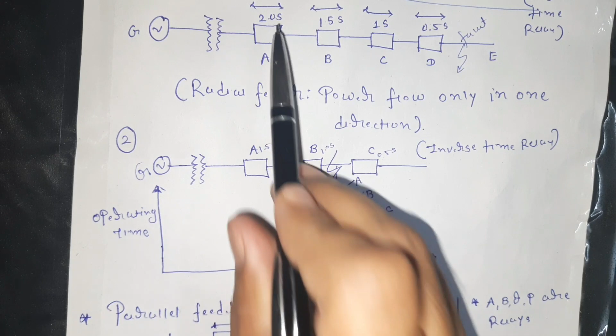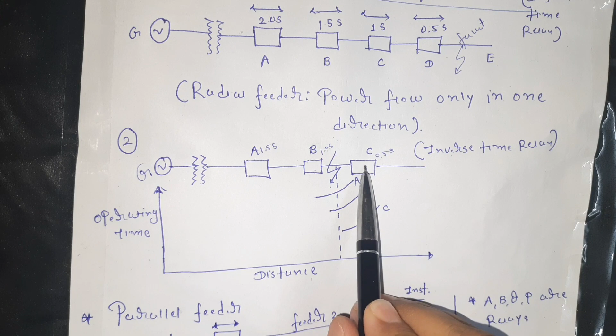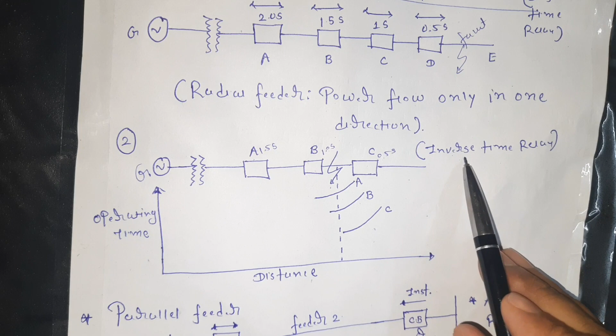Look at the characteristics, operating time versus distance A, B and C. That means if there is a fault in between section B and C, this is the operating time of the relay B. So this particular relay will operate because its time is less than this. So it will operate and this section is eliminated. This is the way how we can get the protection using inverse time relay, right?